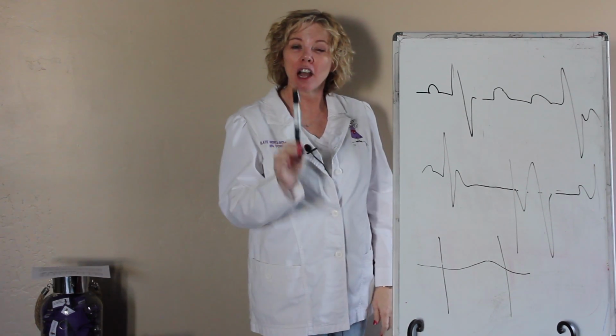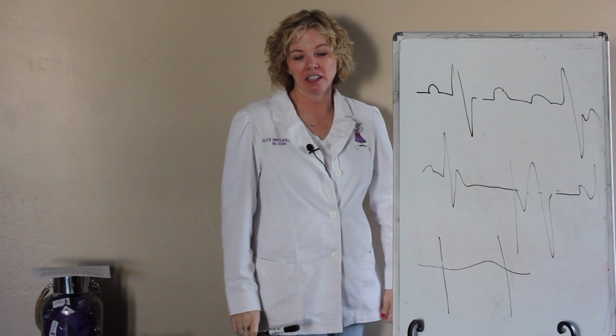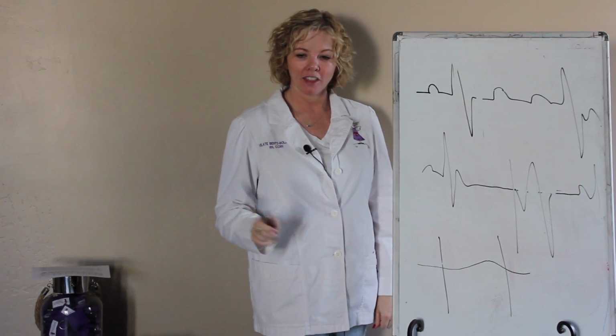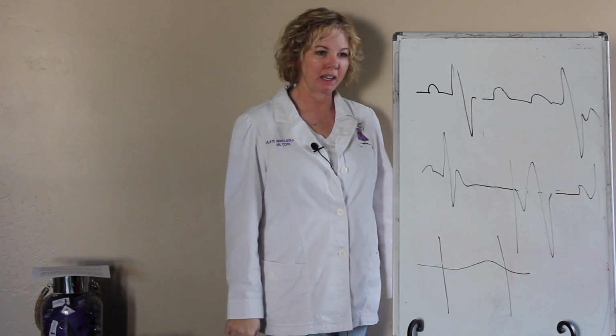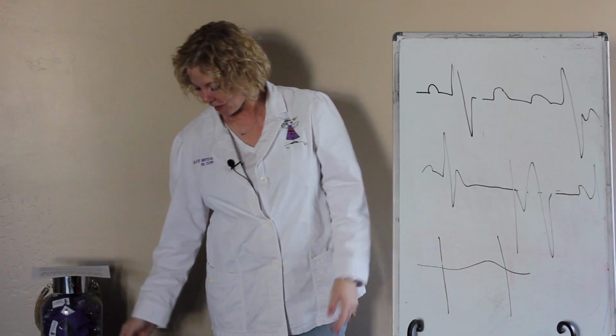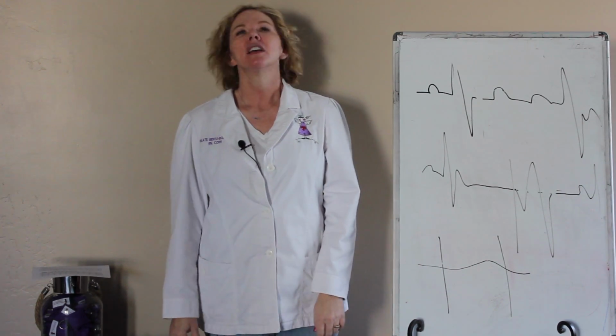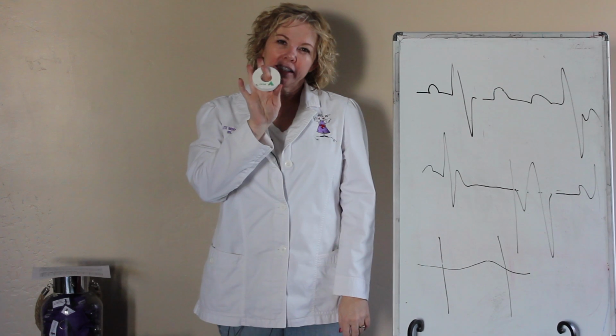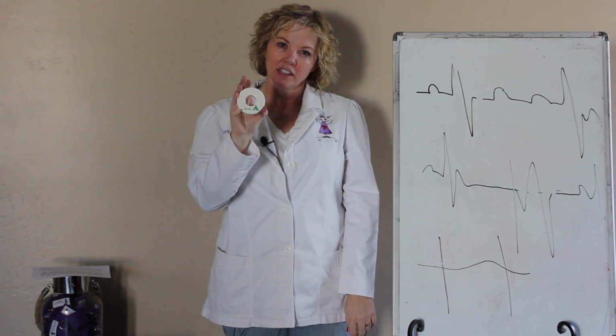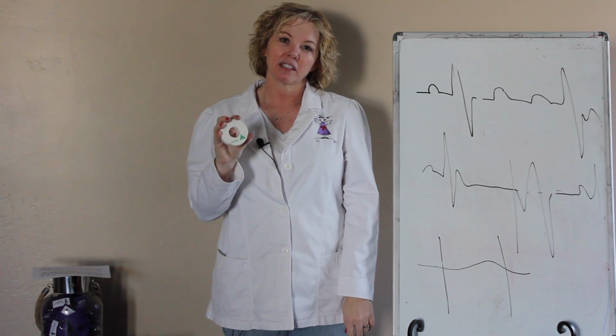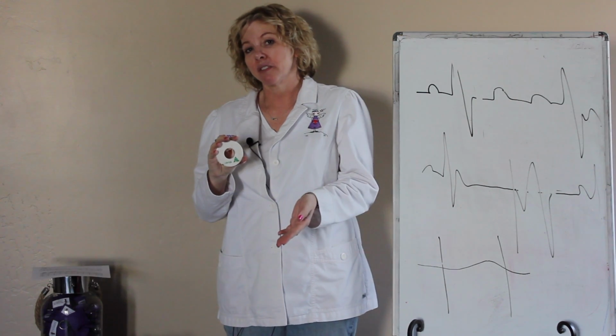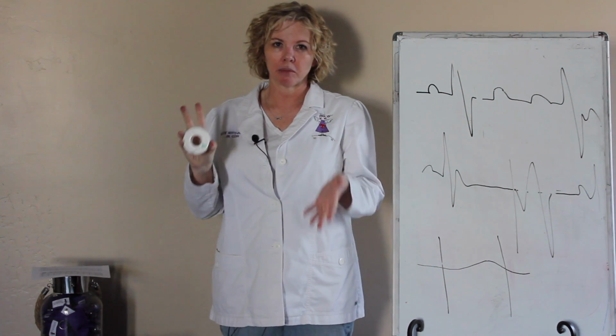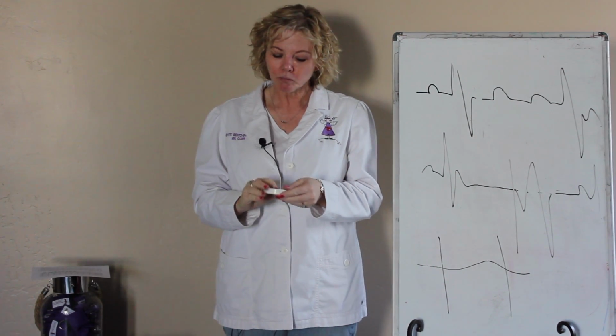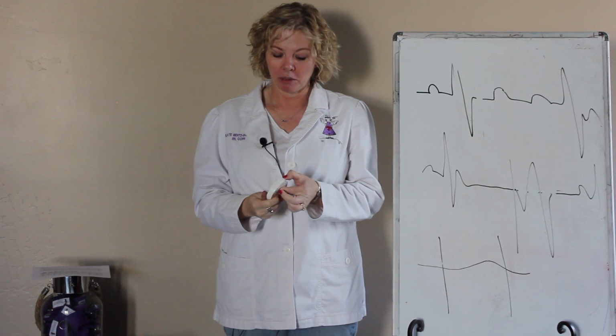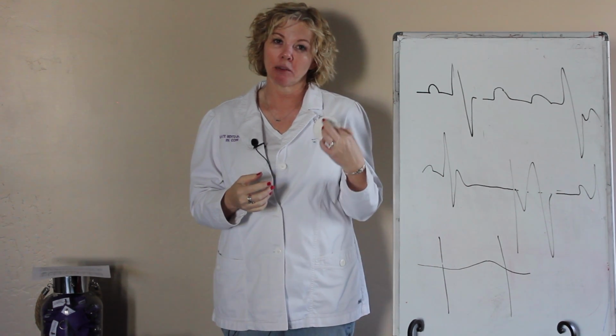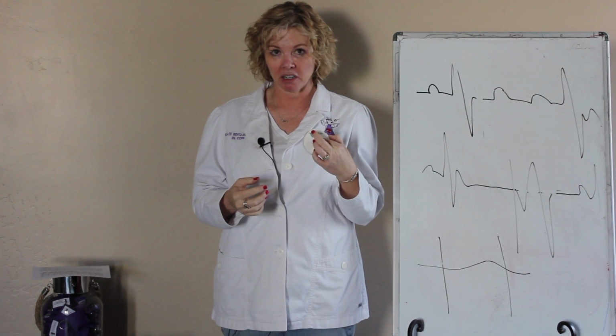I want to tell you one common myth with pacemakers, and then one little thing that you may or may not know about pacemakers that I still want to go over. You may see these magnets at times on your crash cart. These magnets are important for pacemakers and implanted defibrillators, and we'll say just a couple words about implanted defibrillators next. The common myth that many people believe is that if you put a magnet on a pacemaker, it will stop the pacemaker.